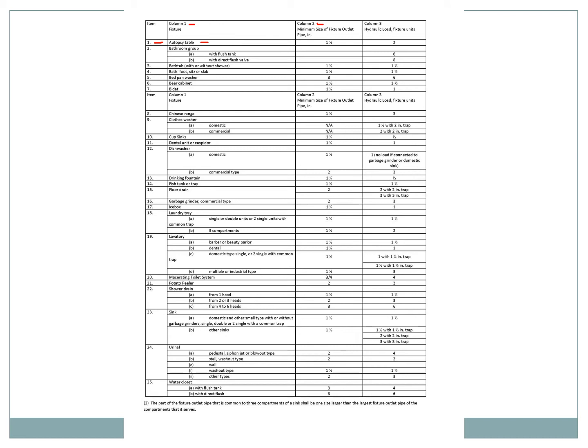Column number three is the hydraulic load or the wet load — the probable amount of water that's going to come through this drain pipe. It's in fixture units, which is that make-believe number originally based on one cubic foot per minute. In the case of an autopsy table, it has two fixture units. We'll come back to this table a little bit later.